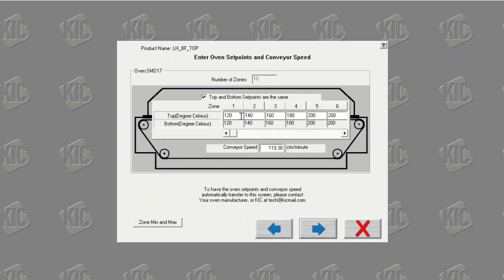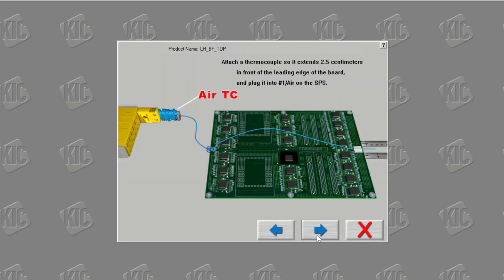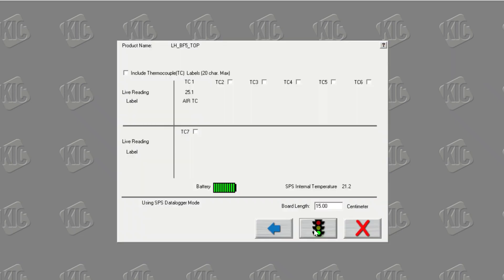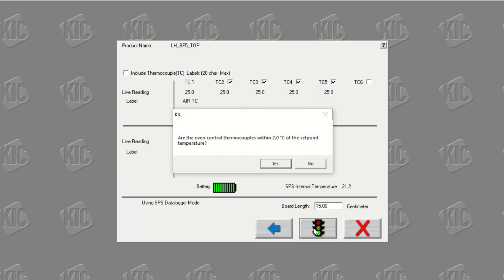In the next step, shown here, just copy the oven speed and temperature set points that you will use for this recipe and click Next. The KIC system will need to be configured to match your current oven configuration. This can be done manually or in an automated process — just navigate through the remaining screens following the prompted messages. Next, select the number of thermocouples you are using before running the profile, shown here. To start the profile, just click on the traffic light and once again follow the instructions showing up on the screen.